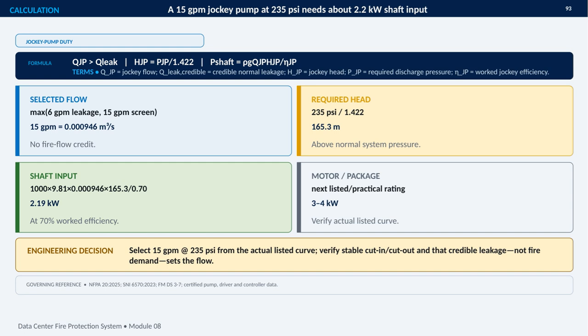Next, we determine the required head from the discharge pressure. Dividing 235 psi by 1.422 gives approximately 165.3 meters, which is above normal system pressure. That head, combined with the selected flow, water density, gravity, and a worked efficiency of 70%, produces a shaft input of about 2.19 kilowatts, rounded to 2.2 kilowatts.